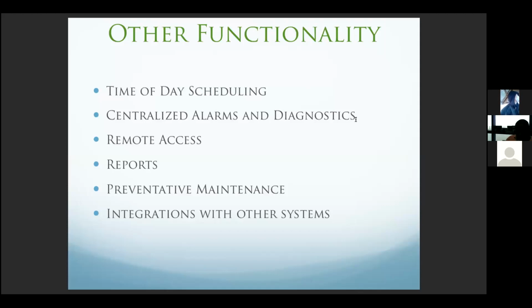It will also show centralized alarms and let you understand what these alarms are, what's causing this alarm, what equipment is causing this alarm, how critical that alarm is. Sometimes you can just get by acknowledging an alarm, or sometimes you need to do major repairs to get things going again.